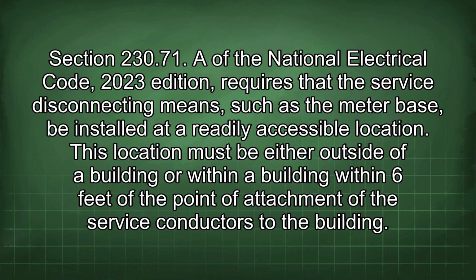Section 230.71 of the National Electrical Code 2023 edition requires that the service disconnecting means, such as the meter base, be installed at a readily accessible location. This location must be either outside of a building or within a building within 6 feet of the point of attachment of the service conductors to the building.